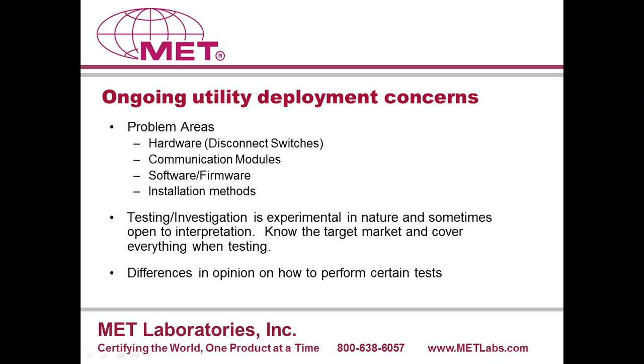Okay, ongoing utility deployment concerns. The problem areas, again, that we hear back, so feedback from utilities. They have issues with hardware in the field, failures. They can't understand why it's gone through the ANSI testing. Disconnect switches they have problems with many times. That's getting better, as I mentioned earlier, but we still hear about that sort of thing. Communication modules, either failing to function in the field or causing problems with the meter itself or even other equipment nearby.